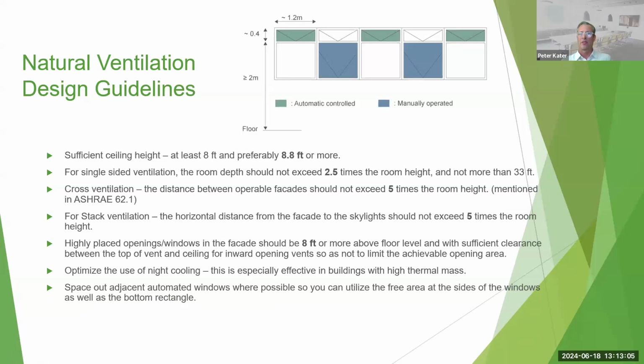And lastly, space out adjacent automated windows where possible, so that you can utilize the free area at the sides of the windows, the triangles, if you like, as well as the bottom rectangle. That means if the windows are hard up against each other horizontally, those side areas of the window when it's open are right up against each other, and the adjacent operable panels don't leave enough space for as much air to flow through the side areas of the opening. Typically, you'll only get air flowing in through the bottom, in the case of an awning window, the bottom rectangular area. So by spacing the windows out, you get a much bigger potential free area, open free area for the air to flow in and out through.